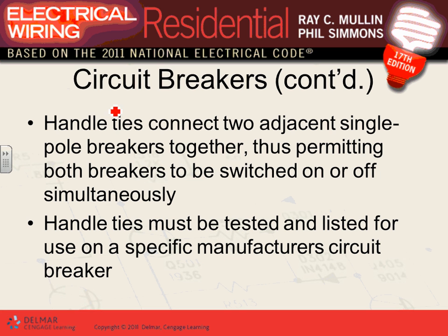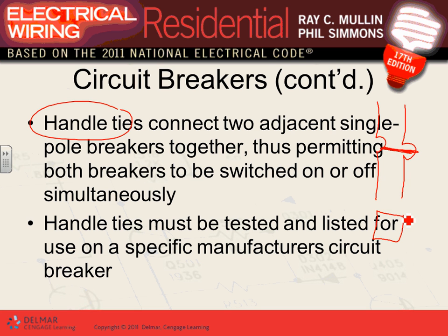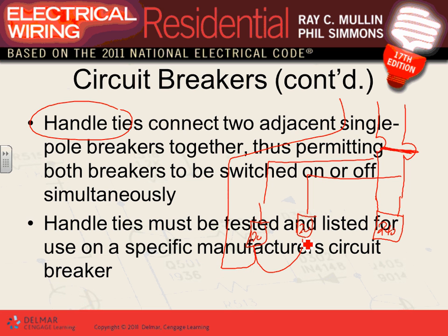The code allows you to use an approved handle tie to connect two single-pole circuit breakers together. You can use it to feed a 240-volt load, or to tie two 120-volt loads on a multi-wire circuit with a shared neutral. The handle must be tested and listed for that specific manufacturer's circuit breakers.